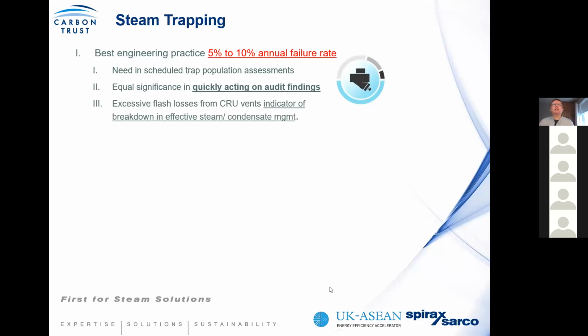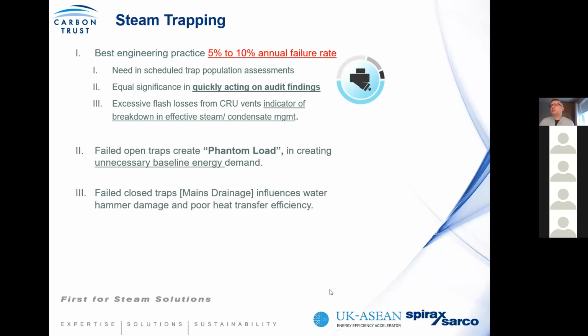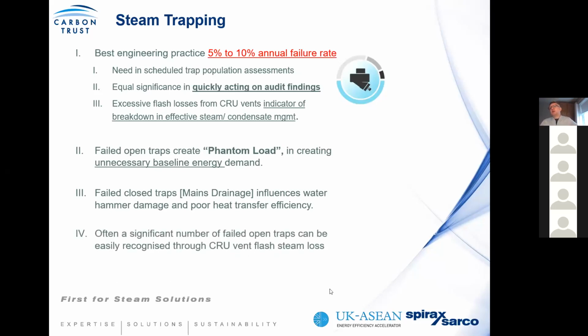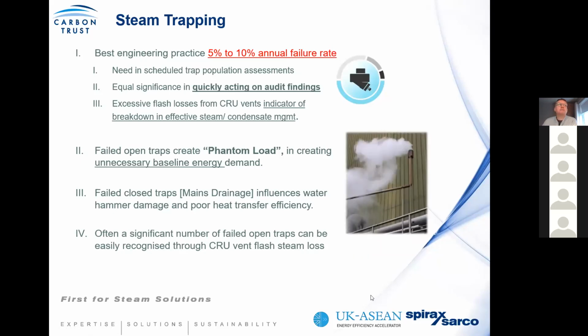Okay, again, look at excessive flash losses as an indicator there's a problem. Failed open traps create what we call a phantom load. So in other words, you could find your steam demand base load is quite high, and this is easily addressable by just challenging your steam traps. Again, we talked about failed closed traps. They influence water hammer and poor heat transfer efficiency. And again, where you have a lot of failed open traps, look to see what's venting from your condensate recovery systems, because that is a good indicator there's something wrong in your system. So look for the telltale signs.